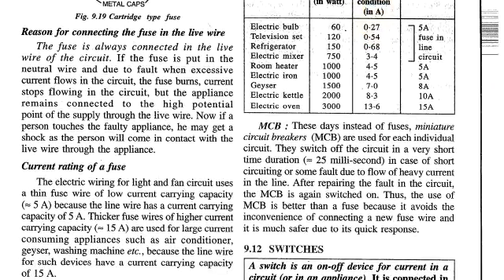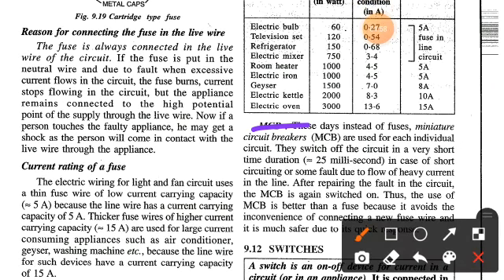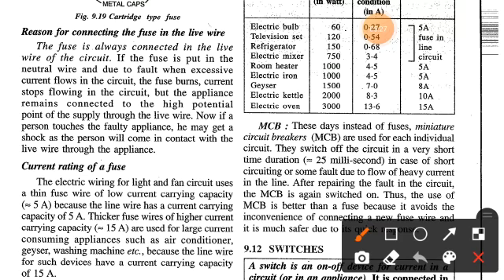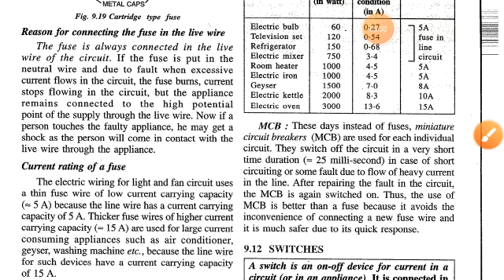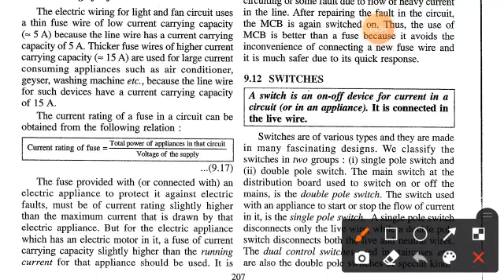Nowadays, instead of fuses, we use the MCB — Miniature Circuit Breaker. MCBs are used for each individual circuit and switch off the circuit in a very short time duration — approximately 25 milliseconds — in the case of a short circuit or fault due to the flow of heavy current. After repairing the fault, the MCB is switched on again. Thus, the use of MCB is better than a fuse because it avoids the inconvenience of connecting a new fuse.